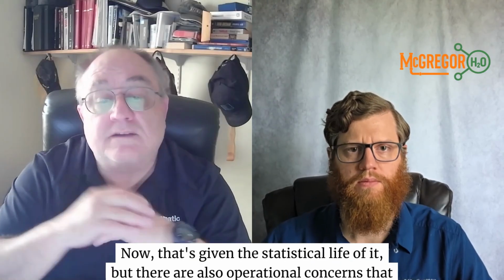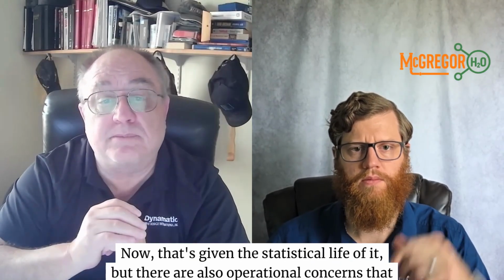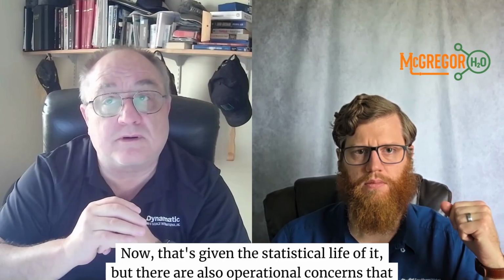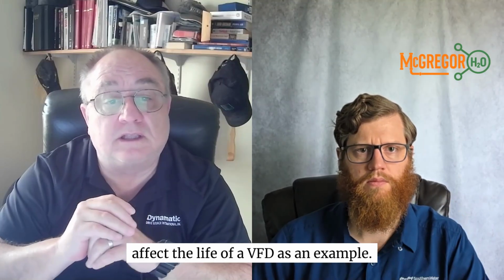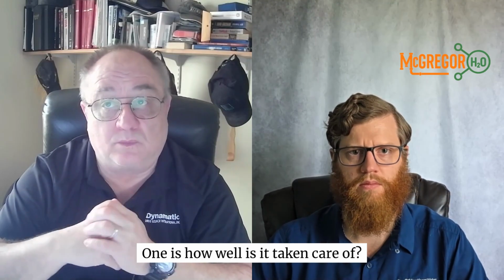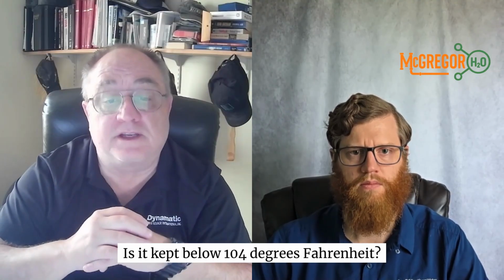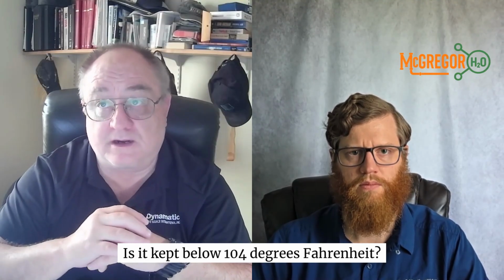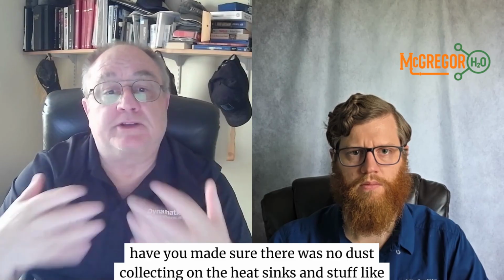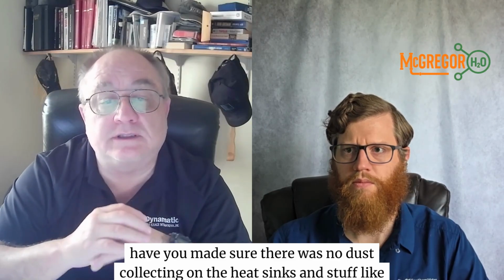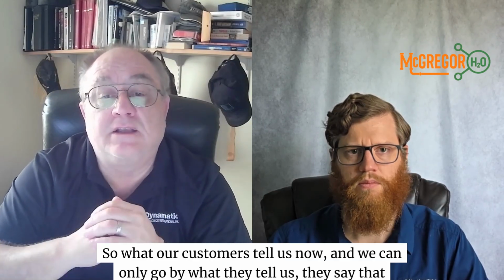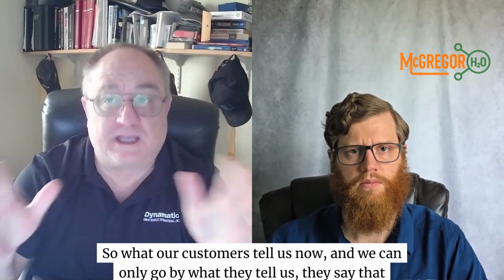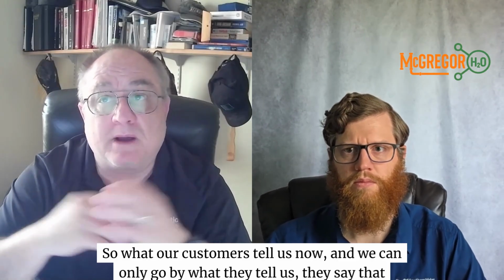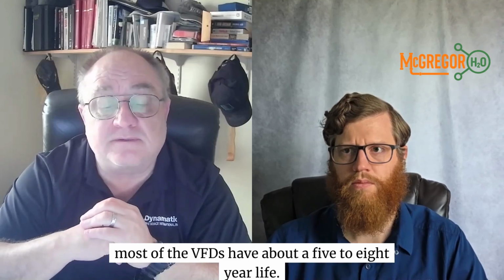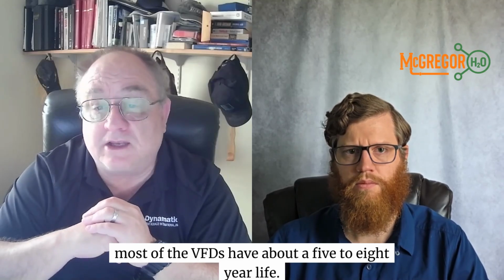Now, that's given the statistical life of it, but there are also operational concerns that affect the life of a VFD as an example. One is how well is it taken care of? Is it kept below 104 degrees Fahrenheit? Have you made sure there was no dust collecting on the heat sinks and stuff like that? So what our customers tell us now, and we can only go by what they tell us, they say that most of the VFDs have about a 5 to 8 year life.